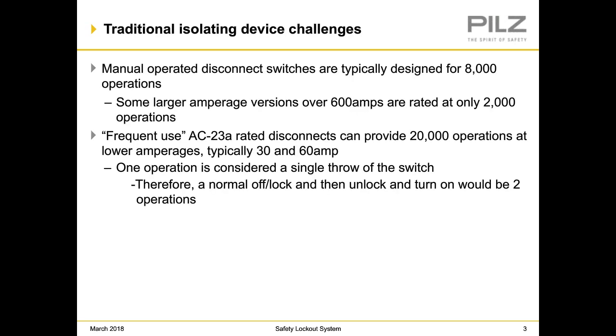So traditional isolating device challenges: essentially, manually operated disconnect switches are typically designed for 8,000 operations. Some larger amperage versions, over 600 amps, are rated at only 2,000 operations. Now there are frequent use AC23A rated disconnect switches, which can provide 20,000 operations at lower amperages, typically 30 and 60 amp. However, you have to consider that one operation is considered a single throw of the switch. So a normal off, lock, then unlock and turn back on would be two operations. So the numbers that you see on the slides would essentially have to be cut in half for a typical lockout tagout cycle.